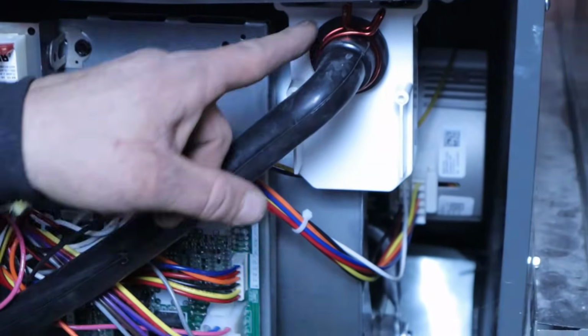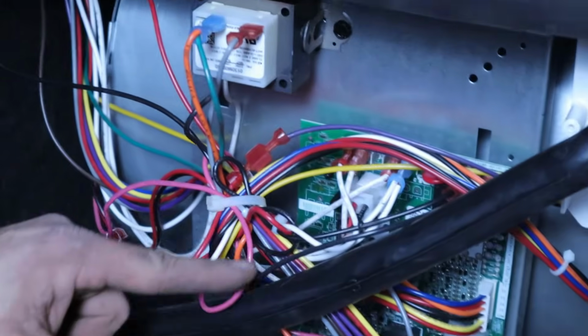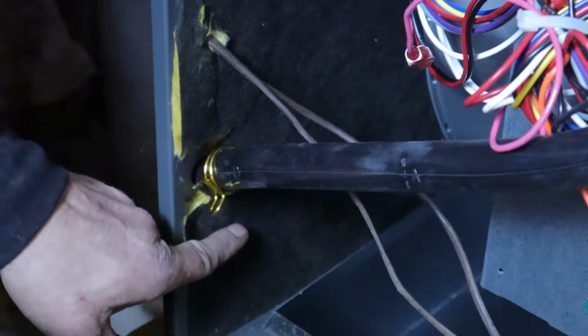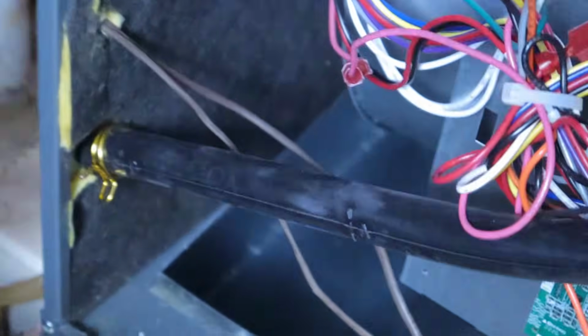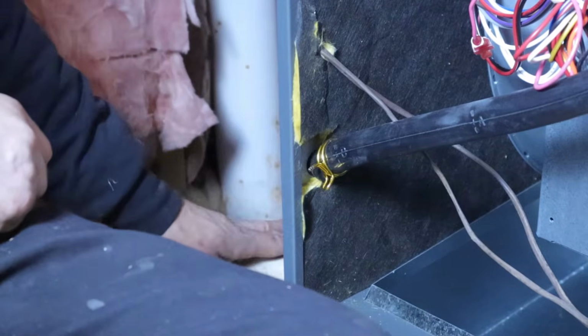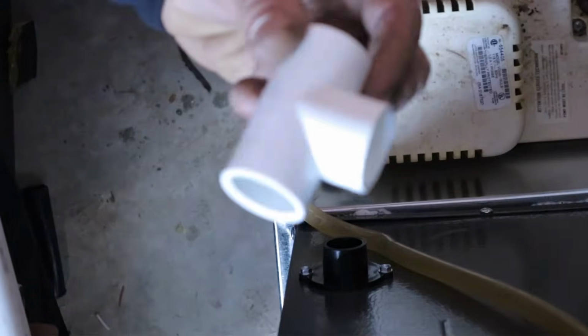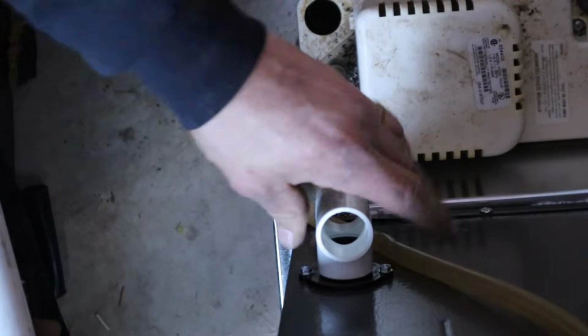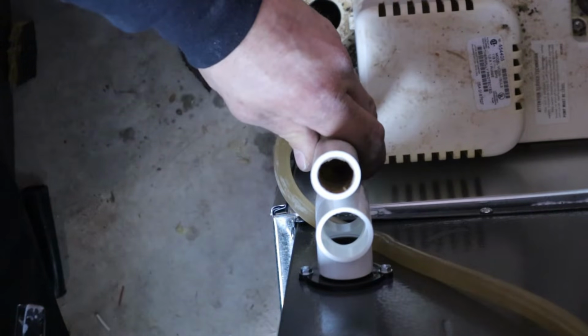We have our drain coming from our trap, going down into our fitting out the side of the furnace, as you can maybe see right there. So now we're just going to take some PVC and we're going to run from this fitting right down into the condensate pump. So what I'm going to do is I'm going to take a T, I'm going to put it right on there, and I'm going to run straight down into the condensate pump.